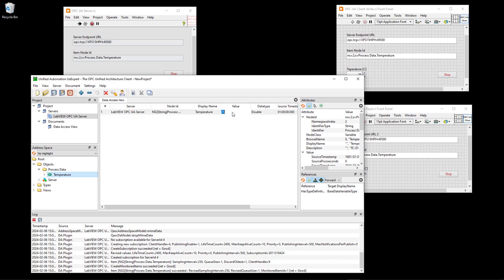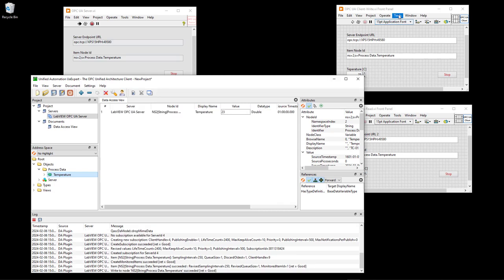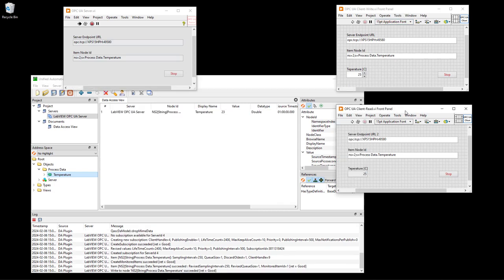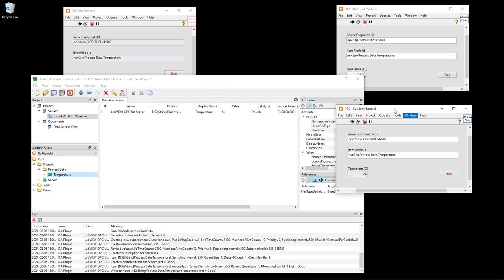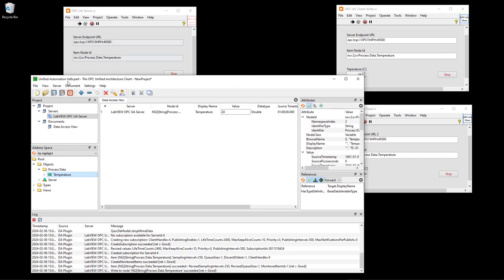I can drag it into this window and the value is 25 for this specific tag. Now let's double click to change the value to 23, then open the OPC UA client that is writing to the same server. The current value written to the server is 23, and you see it's updated here and here. I can change it to 24 and it's updated in the UAexpert software and also in the other client. This is an example of how to use this UAexpert OPC UA client from Unified Automation.